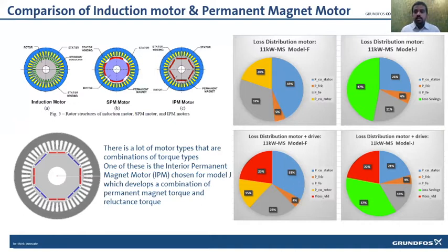And on the technology, as I said, it's a permanent magnet motor technology, which you can see on the right side, where you have a stator with windings distributed over it, and then a rotor with magnets placed on the surface, and here the magnets are integrated within the rotor. This is called IPM, interior permanent magnet motor technology, which Grundfos adopts, which is more sturdy and will have high efficiency in terms of the losses.